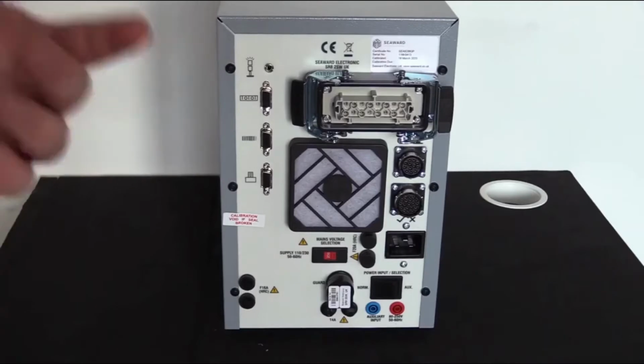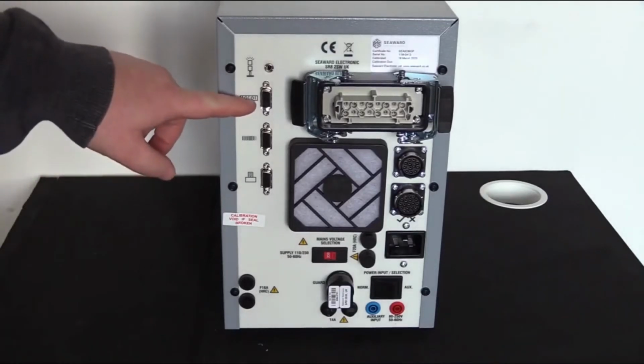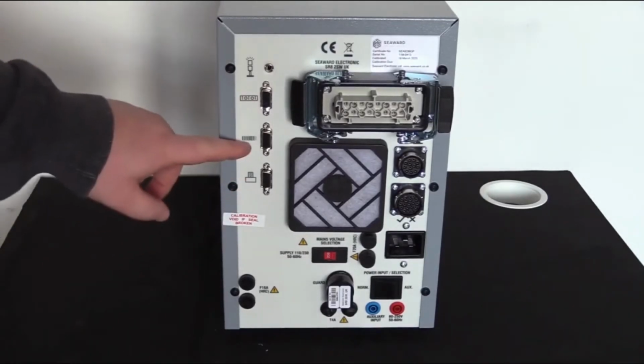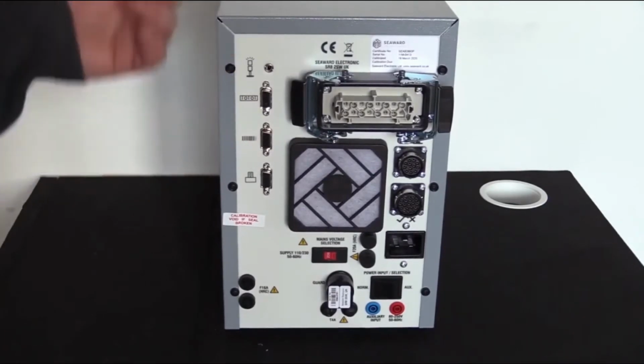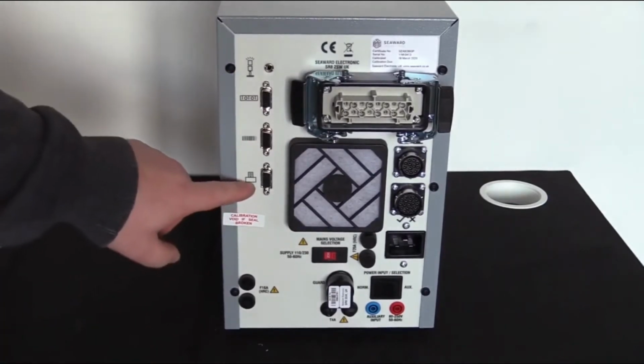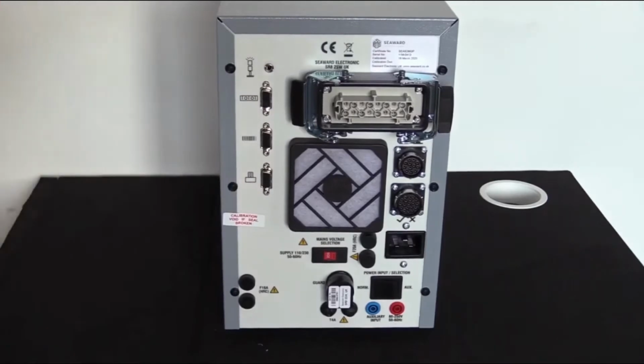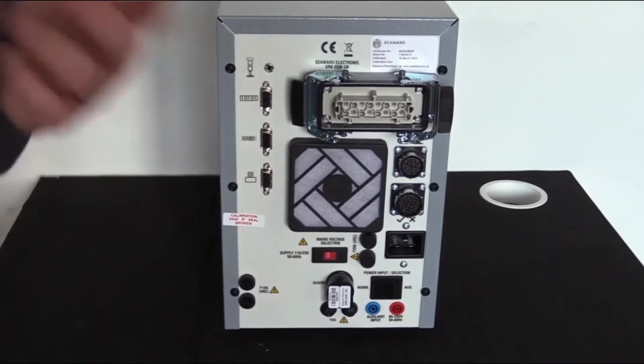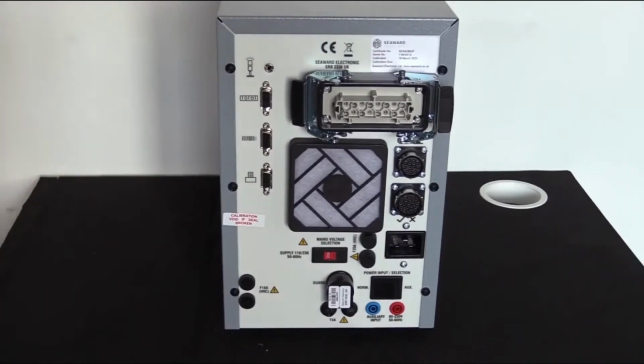Beneath that we have some connection points. So we have our connection for data transfer. We have a connection to a barcode scanner so the operators can scan barcodes. We have a connection to a printer. At the end of the test, the HAL can be programmed to print out pass or fail labels accordingly.